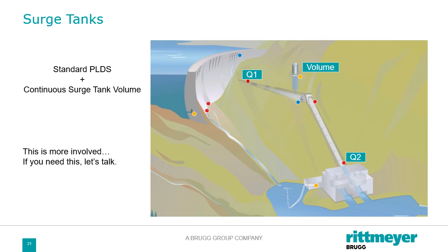That changes during any sort of transient condition, changes in flows or anything else that causes the level in the surge tank to change. Now we have to keep track of that water, because if the surge tank is filling, it can look like there's missing flow when you compare the Q1 and Q2. So you have to account for that volume. That's a volume, whereas the others are flow, so you have to do the additional math to convert that to a flow in the surge tank so that you can do the math correctly. Again, this is a challenge we have faced a number of times. If you have this situation, let us know and we'll put a proposal together for you.